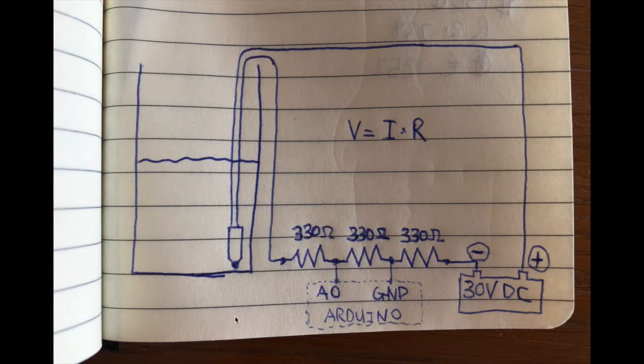The water level sensor I've got has a range of 0 to 3 meters, but since the tanks only go up to around 2 meters, I want to convert 0 to 2 meters into a voltage of 0 to 5 volts. So when the tanks are empty, I'll get a 4 milliamp output, which the Arduino will see as 1.32 volts. When the tanks are full at around 2 meters, the sensor will output around 14.6 milliamps, giving a 4.8 volt reading over the middle resistor. I'm calculating this using Ohm's law: voltage equals current times resistance.